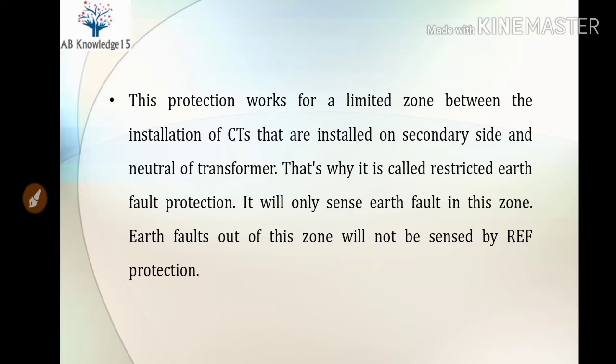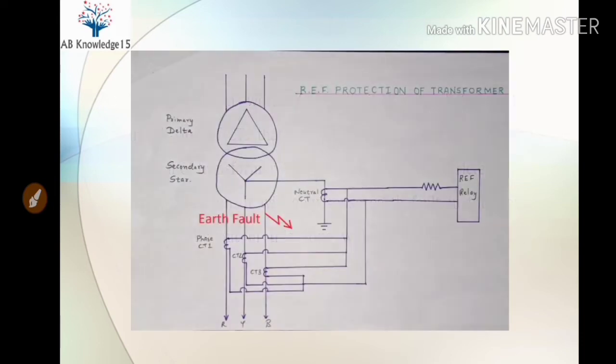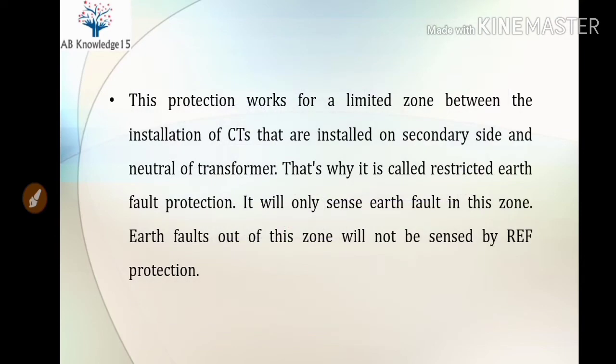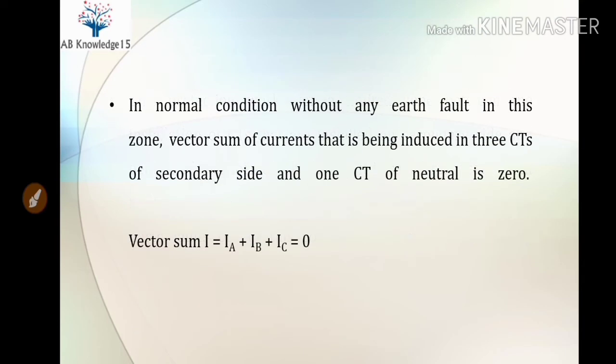That's why it is called Restricted Earth Fault protection — it will only sense earth faults within this zone. Earth faults outside this zone will not be sensed by REF protection. This allows us to determine that the earth fault is only within this zone, helping us identify the location of the earth fault.